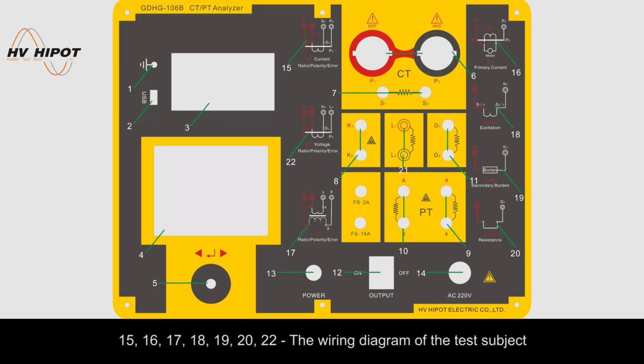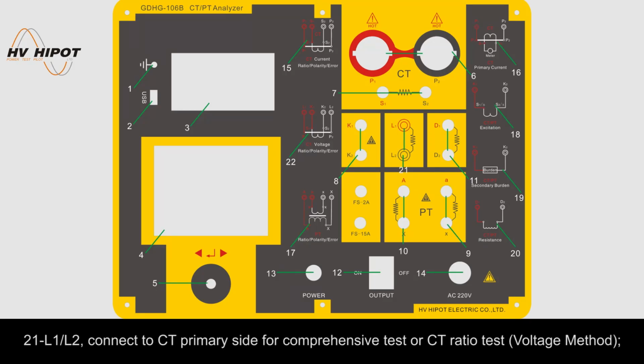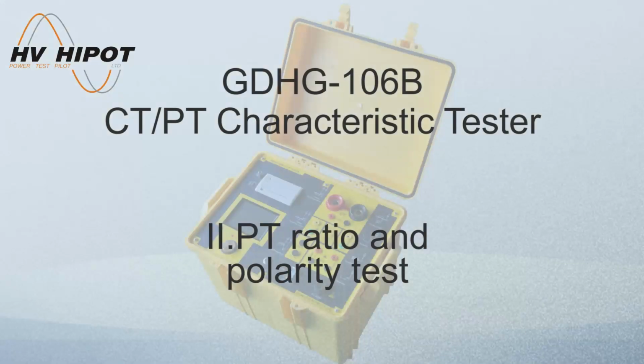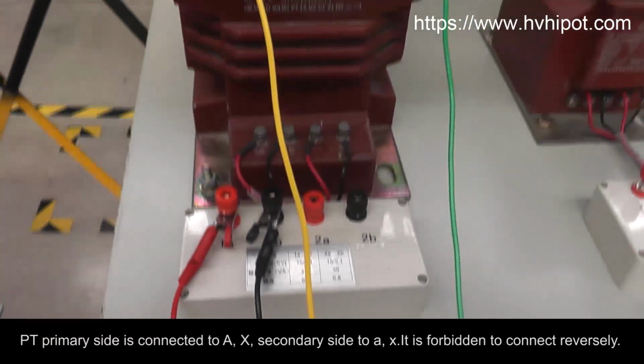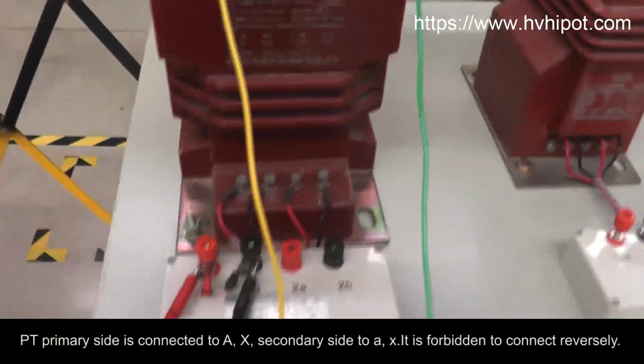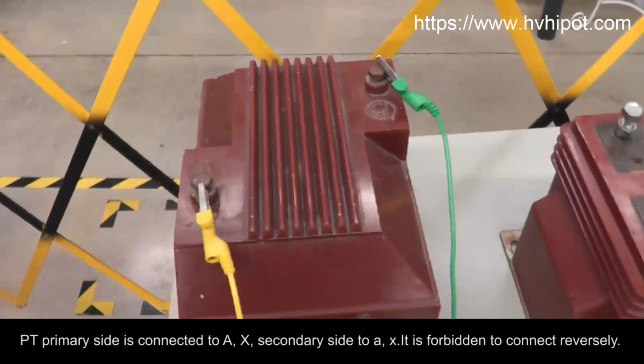15, 16, 17, 18, 19, 20, 22 the wiring diagram of the test subject. 21 L1 and L2, connect to CT primary side for comprehensive test or CT ratio test, voltage method. PT primary side is connected to AX, secondary side to AX, it is forbidden to connect reversely.